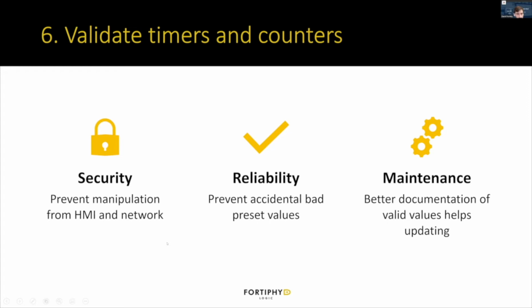For security benefits, this helps prevent some manipulation from the HMI and network, making it slightly harder for the attacker. For reliability, it helps prevent accidental bad preset values by having those double checks in there for the valid ranges. And for maintenance, it helps provide better documentation of valid values as the program gets updated, having that clear documentation of what a valid preset value is.